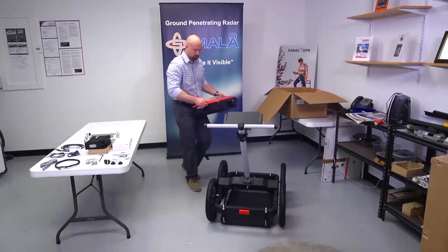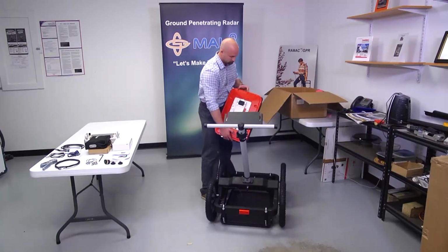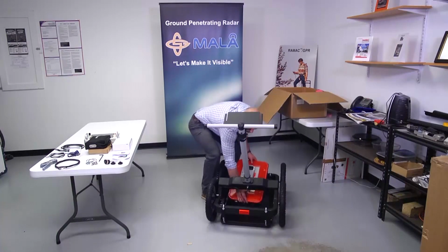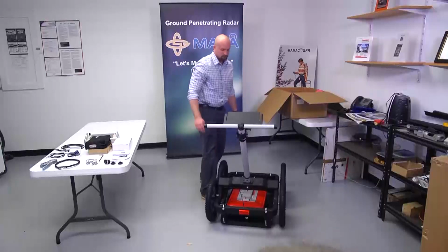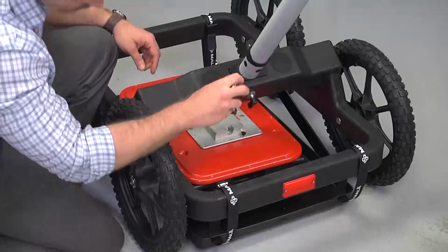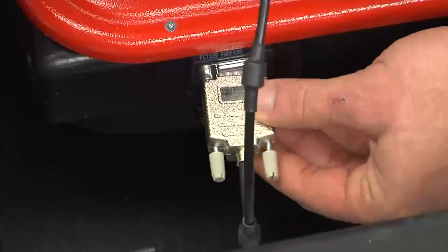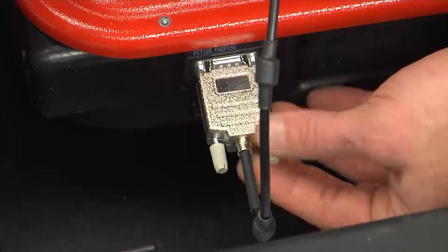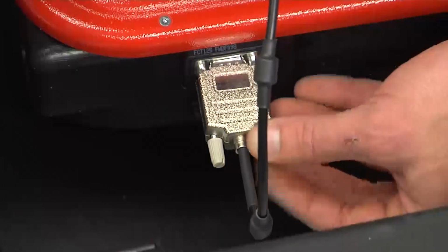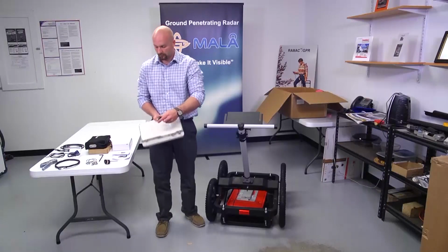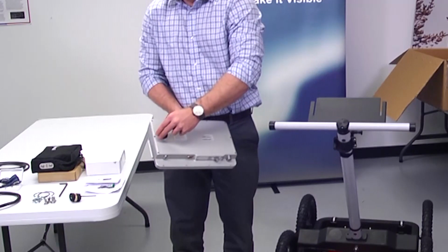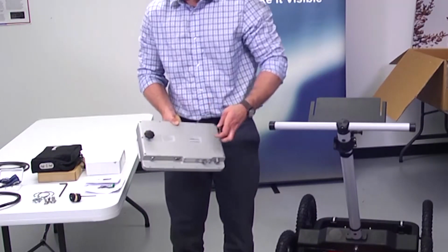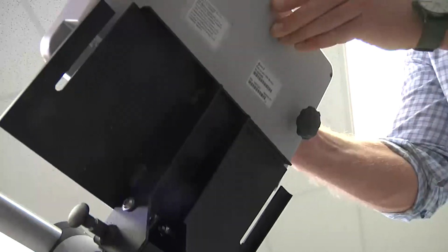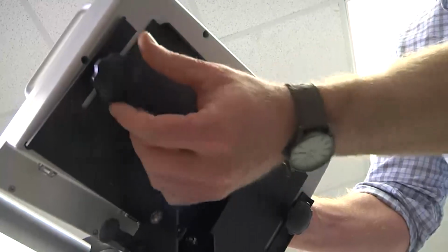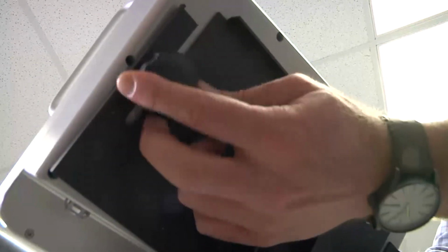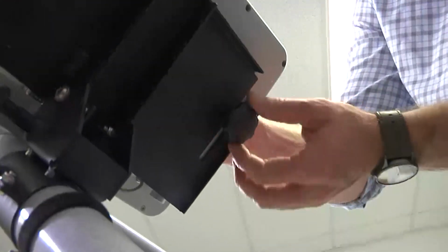To integrate the Easy Locator HDR system components with the RTC cart, begin by sliding the antenna into the front of the RTC. Make sure the PowerCom cable is located in the front of the RTC. Attach the encoder cable connector from the RTC to the rear of the Easy Locator HDR antenna. Do not over-tighten screws. Attach the monitor knobs to the back of the monitor, leaving a gap large enough to slide the monitor into position on the platform by aligning the knob shafts with the slots on the platform. Secure the monitor by tightening the knobs.